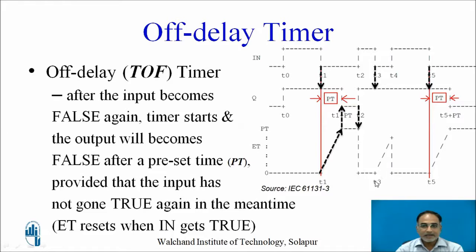At t3, the timer starts and ET value starts incrementing towards PT, but at t4 the input changes from 0 to 1 again and ET resets to 0. Because of this, the change in input is not reflected on the output waveform — you have missed this change in input on the output waveform.